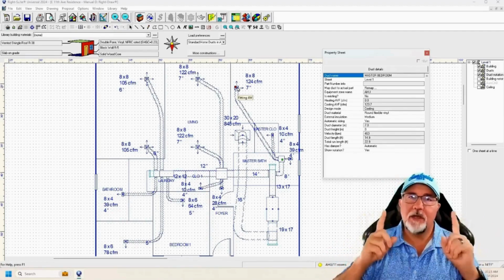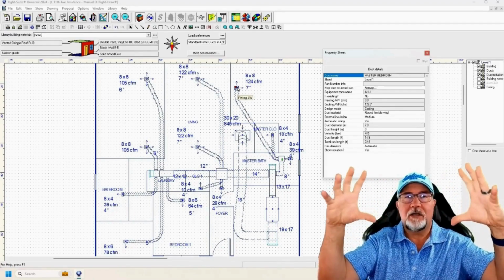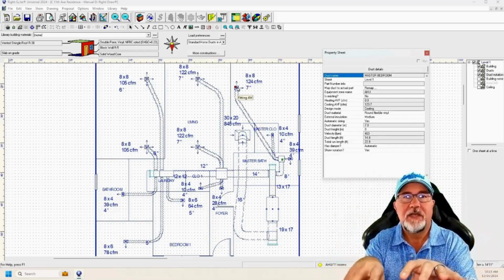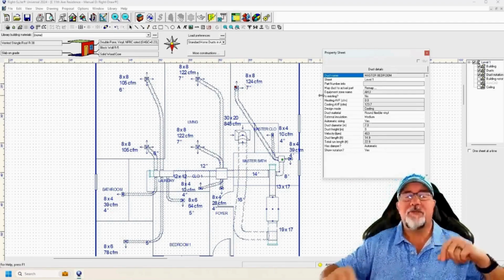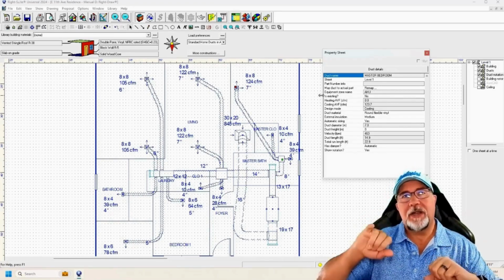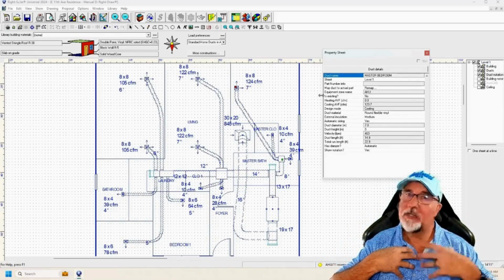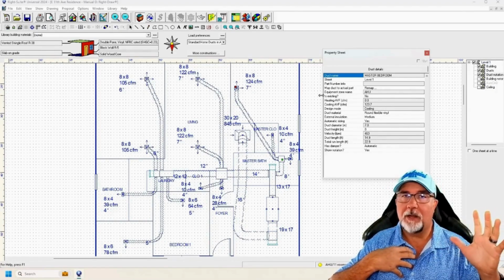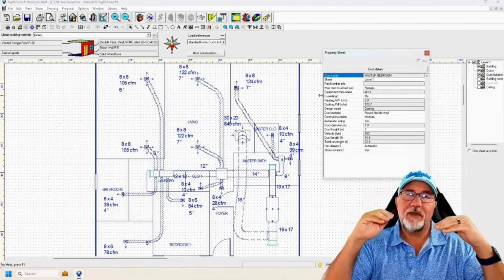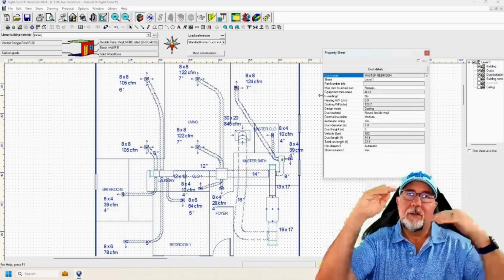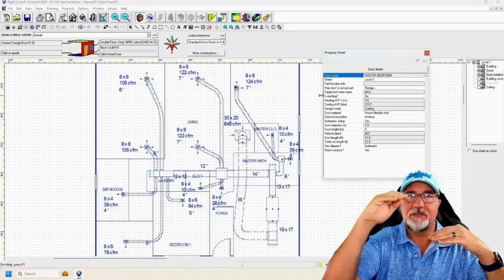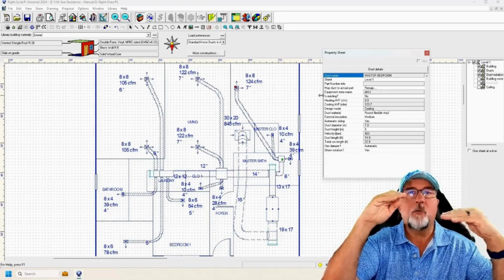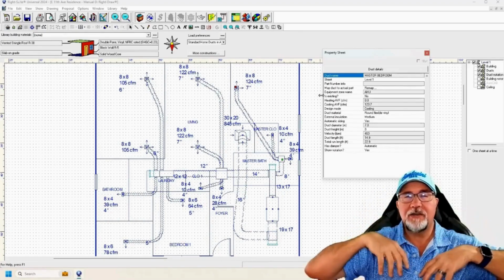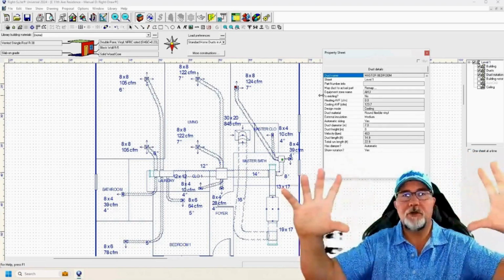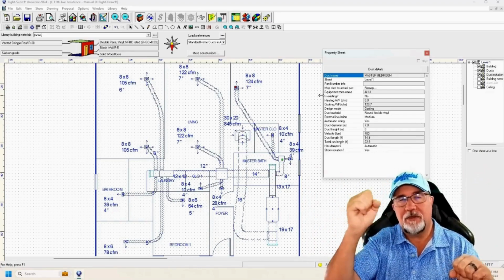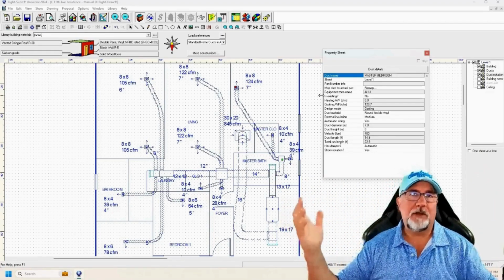So the software, when you do a Manual D, calculates all this to make sure that we're sizing properly. However, here's the other issue. Just because I think a 7-inch duct should have 127 CFMs, and the system tells me that this duct is going to put out 124 CFMs, that's not necessarily the case. That's why I like dampers in the supply, and me personally, I like return dampers as well. I know I'll get a lot of pushback on that, but if you want a slight positive pressure in a room, and you have a return that's not regulated, then if I have 124 CFMs coming in, I need to be able to regulate that there's 120 CFMs going out of the return so that I'm slightly positive. But if I just have an open 7-inch duct and an open 12-inch return duct without the ability to regulate it with a damper, then I'm like a broken clock. I might be right twice a day. And that's not what it is.